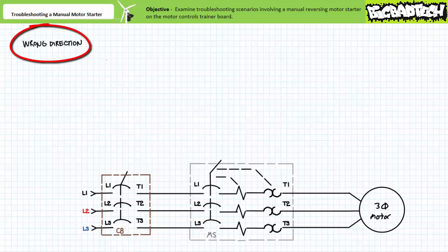Recall that a hardwired manual motor starter fixes direction of rotation. If you are called in to troubleshoot a scenario in which a manual motor starter rotates the motor in the opposite of the desired direction, you need not spend more than a second in diagnosing the problem. The manual motor starter, motor, or some other circuit element has been improperly wired with the incorrect phase sequence. To reverse the direction of rotation, a technician must lock out and tag out the system, swap any two hardwired phase connections, return the system to service. Too easy.